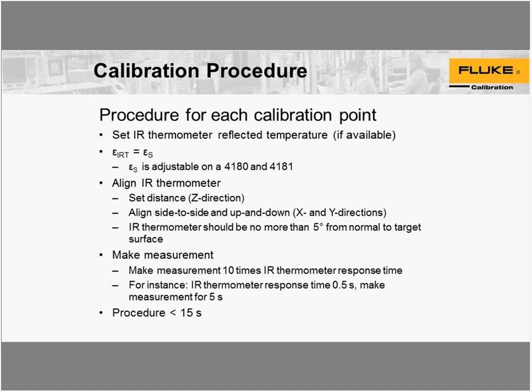To align the IR thermometer, you need to set the distance — the z-direction in Cartesian coordinates. Set the distance to your measuring distance for calibration. Then align the IR thermometer from side to side and up and down — the x and y directions. When this part of the process is done, the IR thermometer should be no more than 5 degrees from perpendicular to the target. That should be pretty easy for a laboratory to maintain.